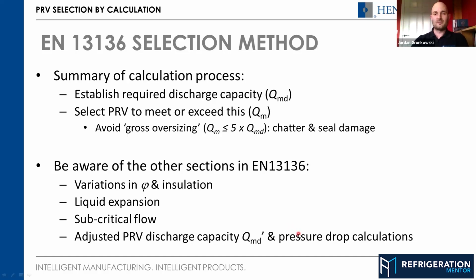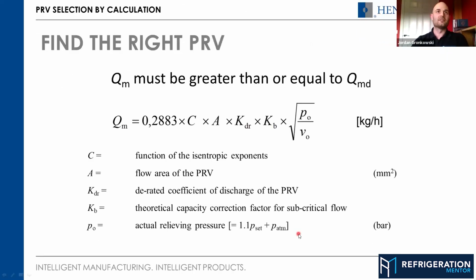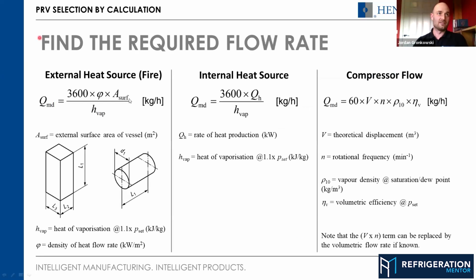It may do. So remember, if we skip back a slide, what we're doing for the external heat source method is looking at the surface area of the vessel and various other terms. The reason we're looking at the surface area is that this calculation is trying to figure out, if there is a fire in the plant, how quickly the heat is going to be absorbed into the vessel. That's why it's worried about surface area. A lot of people think it's the volume of the receiver that matters, but no, it's the surface area, because it's how quickly the heat is absorbed that will determine how quickly the pressure and temperature rise inside the vessel. Therefore, it determines how much capacity the valve needs to vent that safely and stop it getting above a certain limit, like 10% over.